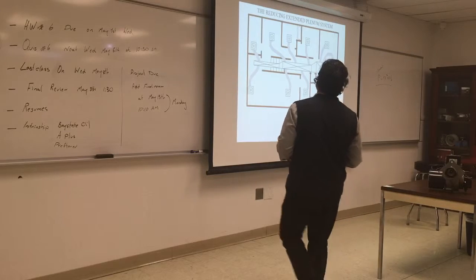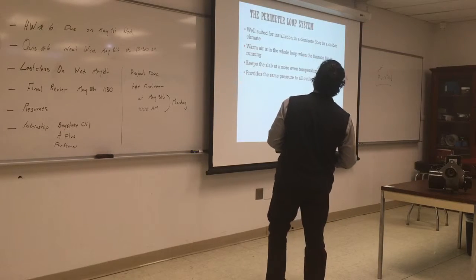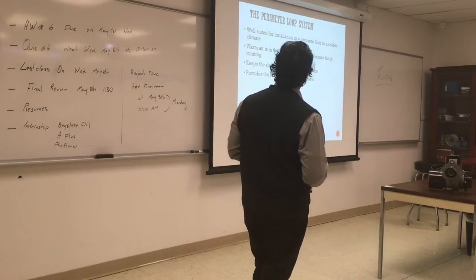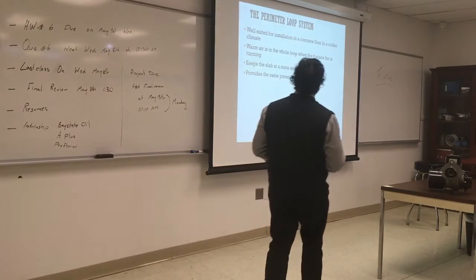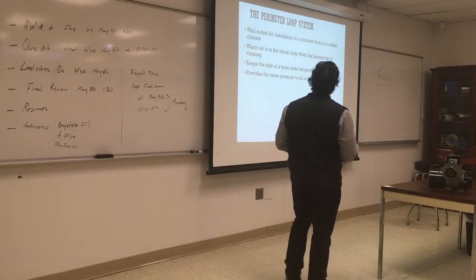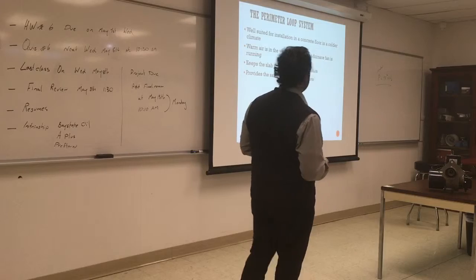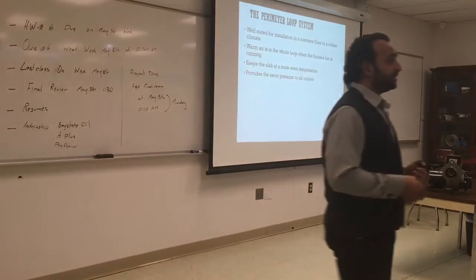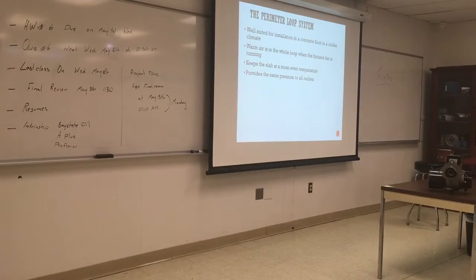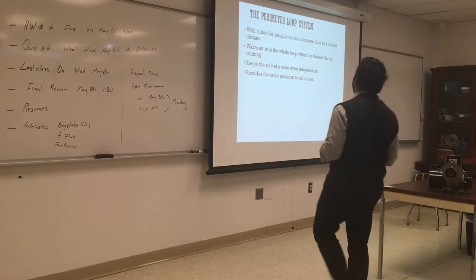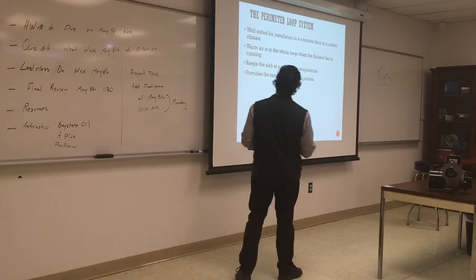And this is the reducing plenum. So it's very suited for concrete. This is the perimeter now. So the perimeter goes around the structure. It's very good for concrete floor and colder climate. It's one of the least expensive ways to put in a duct system. I've seen it also in a crawl space, because you go in the bottom and you just go around the room, put it in the top, or anything in the top or the bottom.